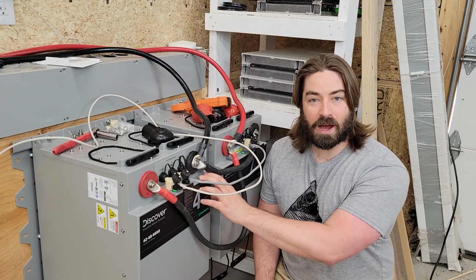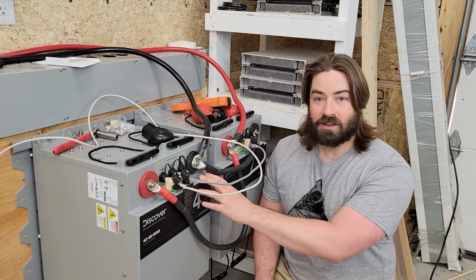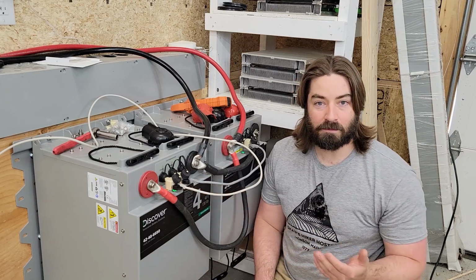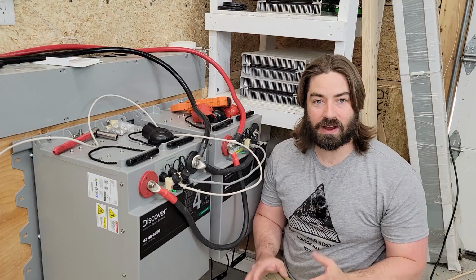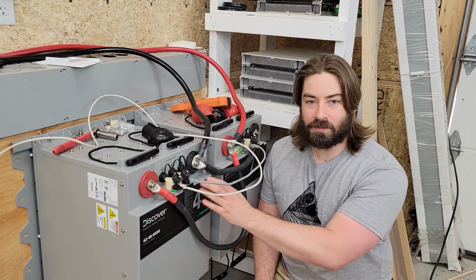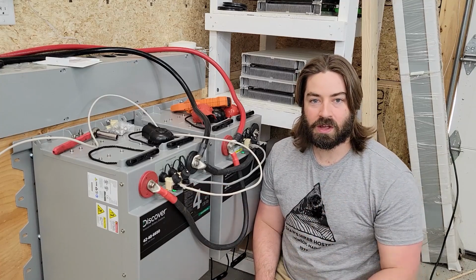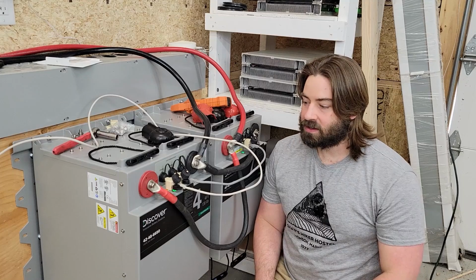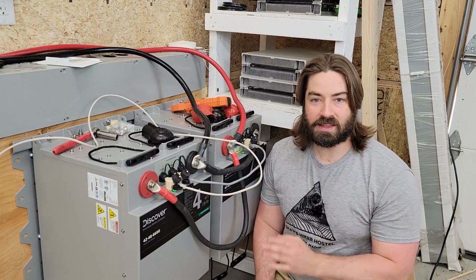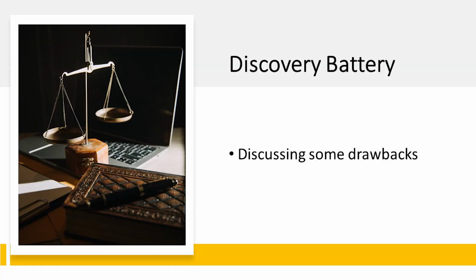The BMS was outstanding. We did 219 amps for a minute, which is incredible. Typically a BMS is going to shut off as soon as you go a little bit over its rating, so I was really impressed with the overload test.